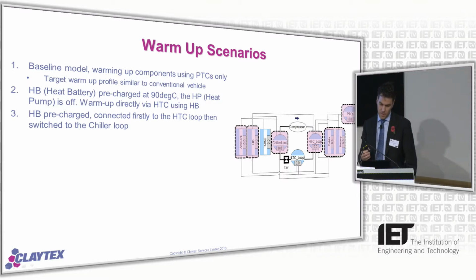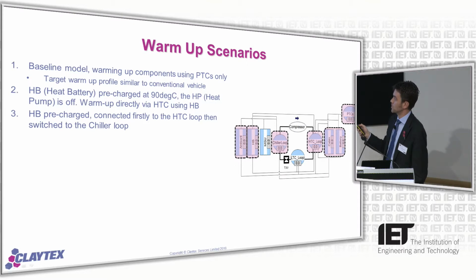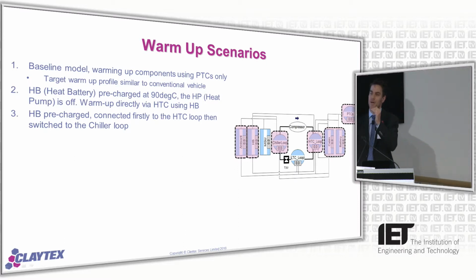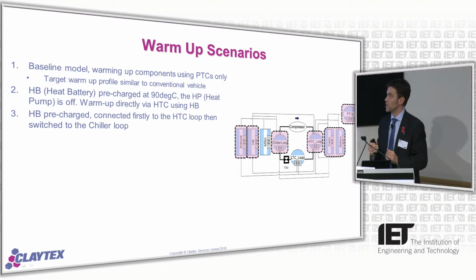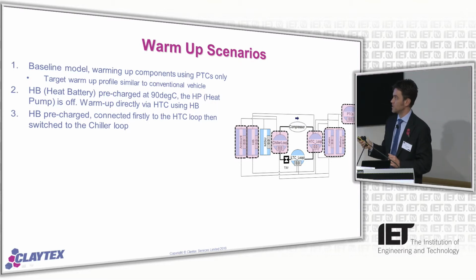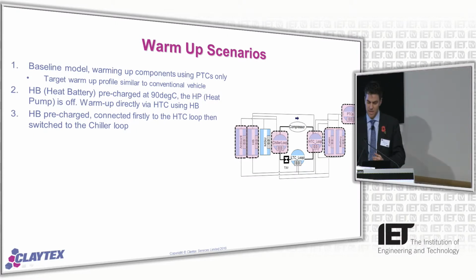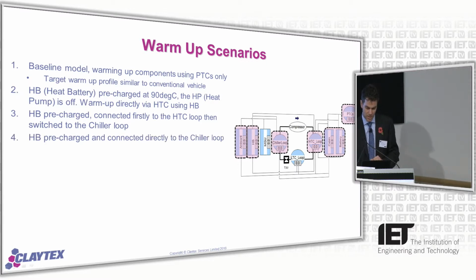The second, or third, scenario has a heat battery pre-charged and connected firstly to the high temperature loop, this time with the heat pump actually working. When we cannot extract any more energy from the heat battery - when the temperature of the high temperature loop and heat battery have stabilized or equalized - we carry on extracting energy by connecting it to the chiller loop, chilling the heat battery down to a much lower temperature than if we just connected it to the high temperature loop.